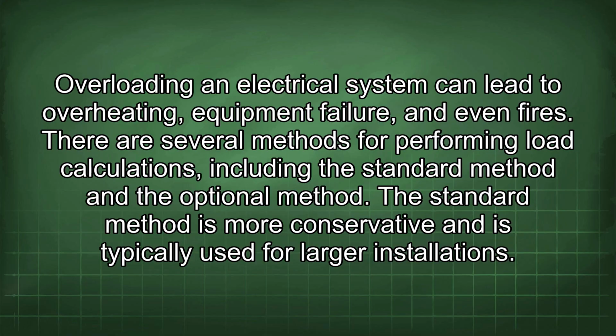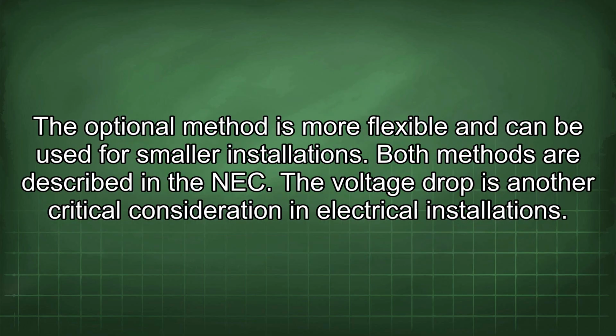There are several methods for performing load calculations, including the standard method and the optional method. The standard method is more conservative and is typically used for larger installations. The optional method is more flexible and can be used for smaller installations. Both methods are described in the NEC.